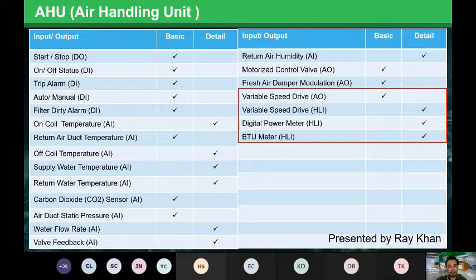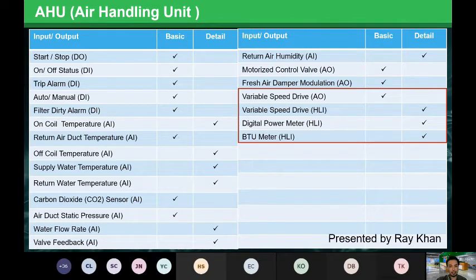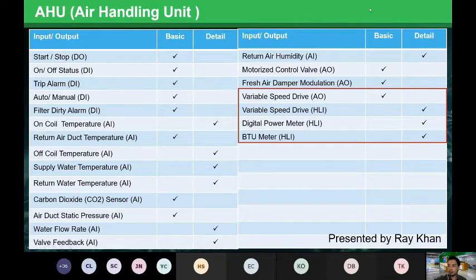For variable speed drives, you will need to cater an output or use a high-level interface. Nowadays, depending on the selection of the variable speed drive, most on the market run on high-level interface — you can choose Modbus or BACnet protocol to communicate with the drives. Digital power meters also commonly run on high-level interface using Modbus, and likewise for BTU meters.